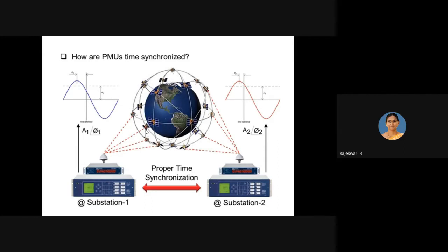The satellite gives a pulse per second, which is used as a time reference. With respect to that time reference, measurement is performed at a particular bus, giving A1 angle phi1 for substation 1. Similarly, the same structure is used at another substation, giving A2 angle phi2, where phi2 is the phase angle of the voltage at that substation. Substations are nothing but buses in the system.